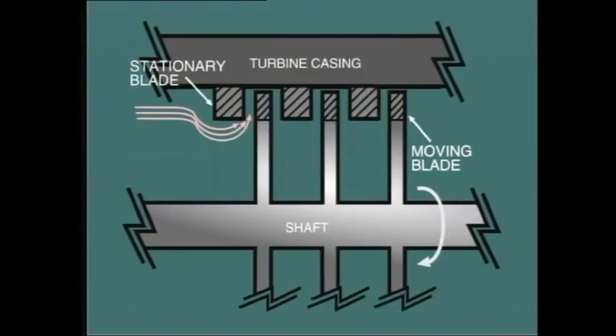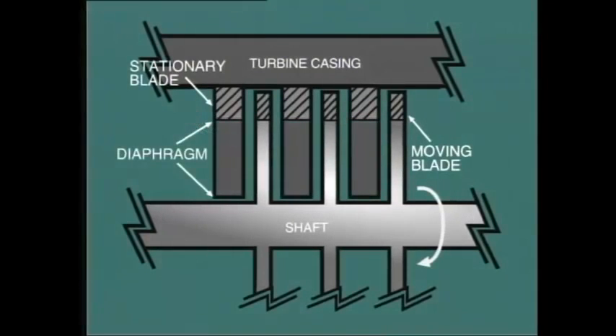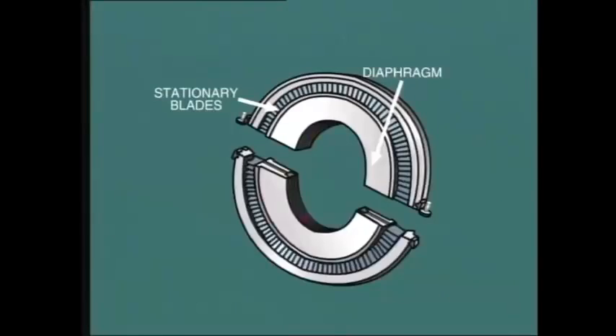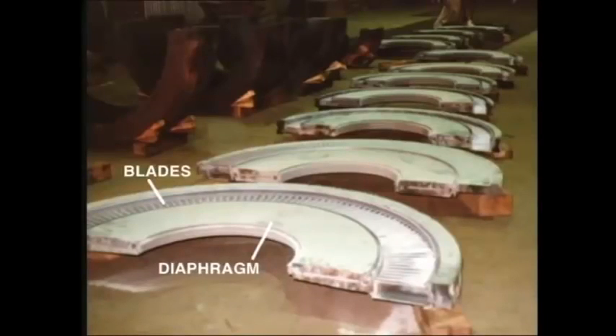In order to prevent this, a shield known as a diaphragm is constructed, extending all the way from the inner diameter of the stationary blade down to the shaft, leaving a small clearance to allow rotation. In practice, the stationary blades are inserted into the diaphragm like this, and the diaphragm itself is fixed into the turbine casing. When diaphragms are removed during maintenance periods, they look like this.